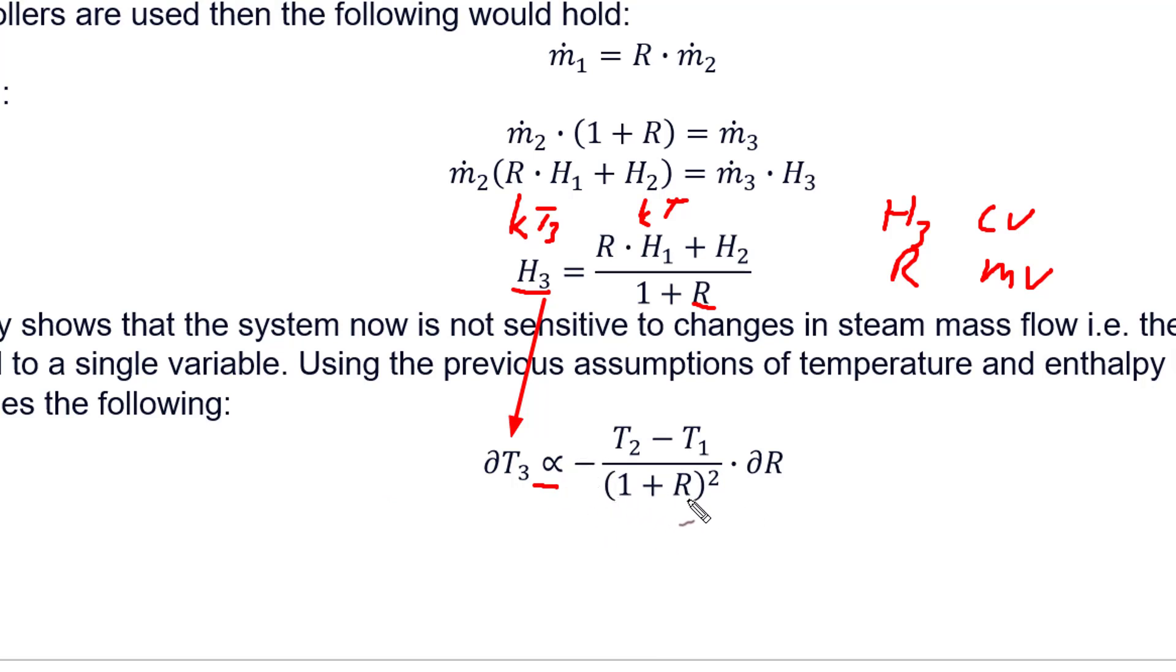I've removed all the constants. Now look very carefully at the equation we have. We're manipulating ratio, that now becomes the variable that we are manipulating. So it's R, MV, and we're trying to control T3. Let's look at that denominator. What is R normally? R is the ratio of the boiler feed water to the inlet steam, and normally it's a very small number. Let's say R is around 0.1 percent. Look at that denominator—it is a constant basically, it's close to one.